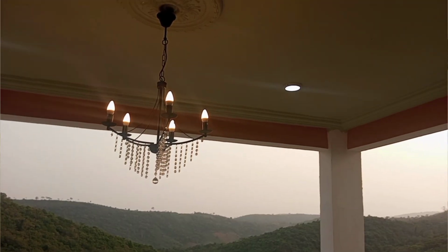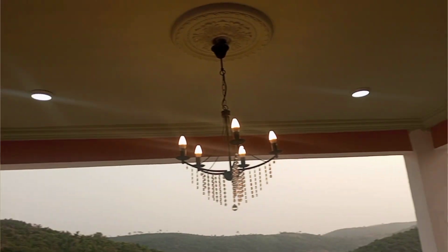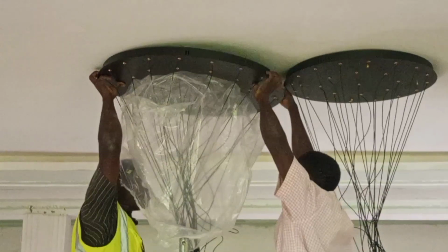So, in assuming the power rating of the lighting system in this room, you cannot just do it by counting the number of rooms and assuming anything. You have to have an idea of the things that will be in that room, like the number of lamps, the type of lamps, the number of fans, and if there are other things. All these are going to affect your number of circuits in that facility, and it's going to affect the number of breakers you'll be needing to protect the lighting systems.